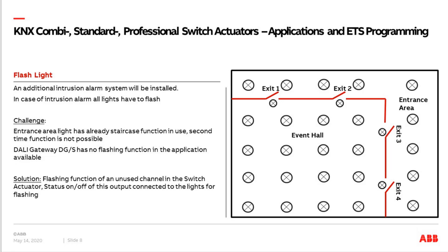The solution is to use a free output in the switch actuator — an unused channel with no circuit behind — and program the flashing function there. We can also program a status telegram, a status feedback from that switch actuator channel. This status as a telegram on the bus gives us the information whether the light is on or off. With a flashing function, it changes from on to off and vice versa — a real status of the relay position. This I assign to the other channels A and B, and also to the DALI gateway. Then it works as a kind of logic for flashing light.